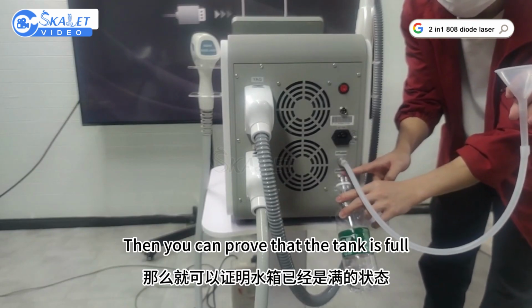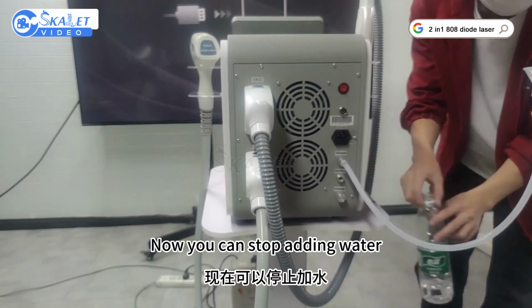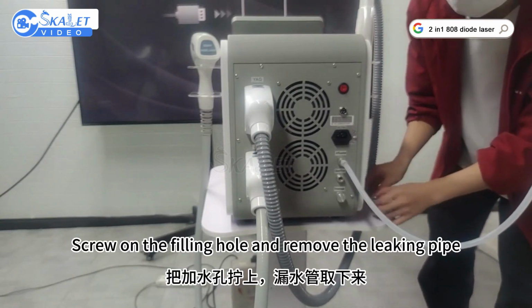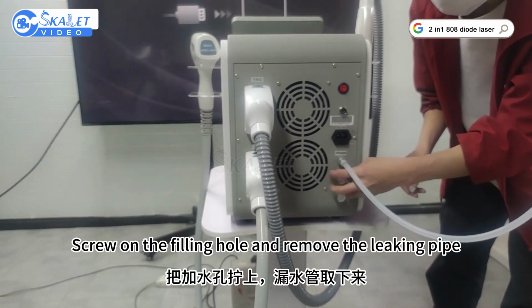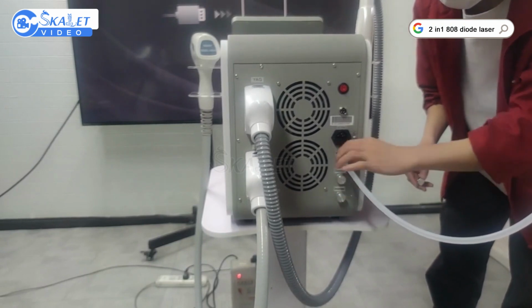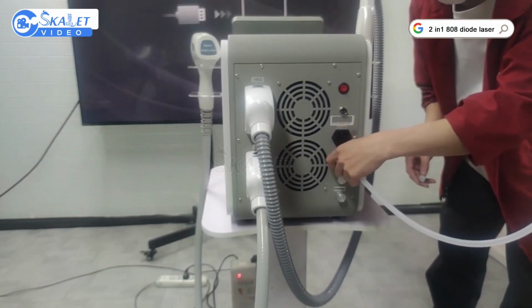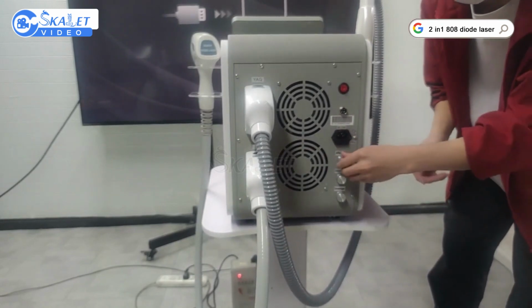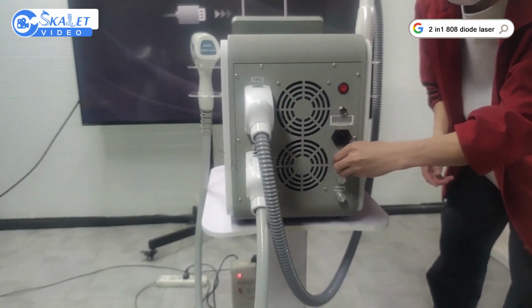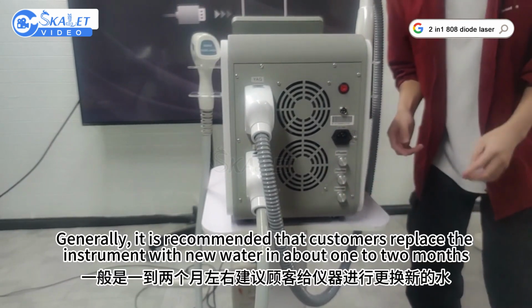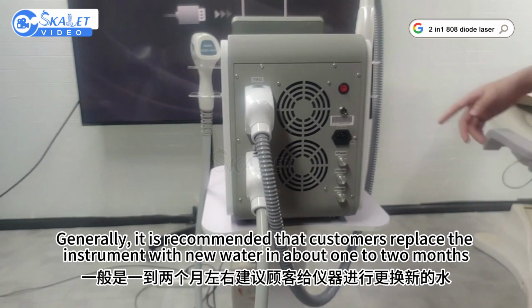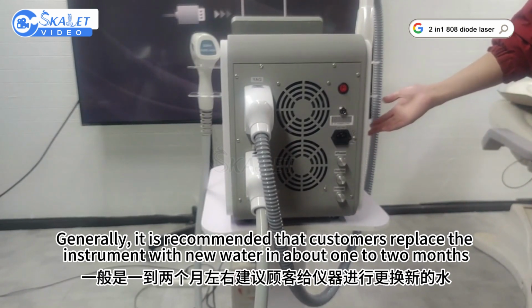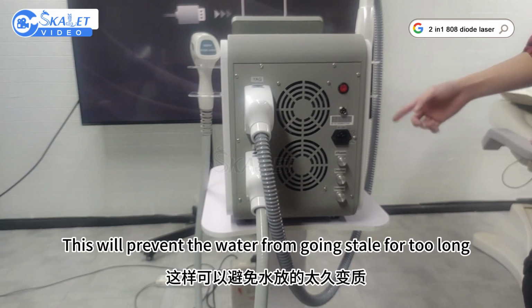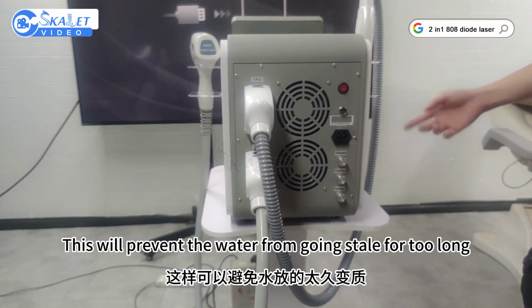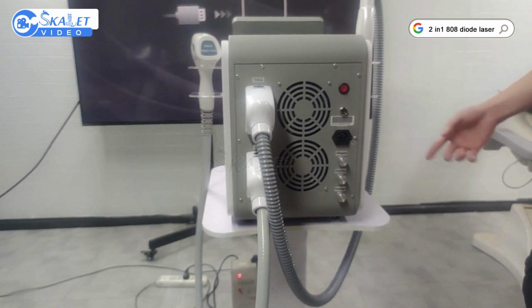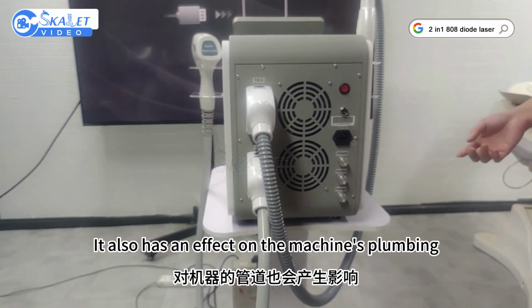Then you can prove that the tank is full. Now you can stop adding water. Screw on the filling hole and remove the leaking pipe. The third hole is the drain hole. Generally, it is recommended that customers replace the instrument with new water in about 1 to 2 months. This will prevent the water from going stale for too long. It also has an effect on the machine's plumbing.